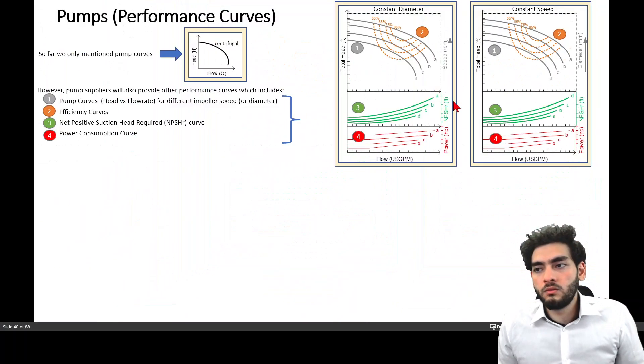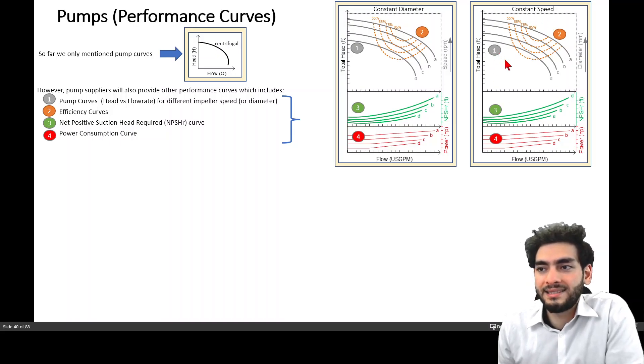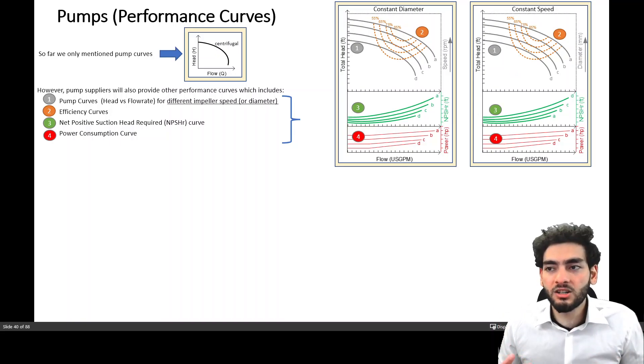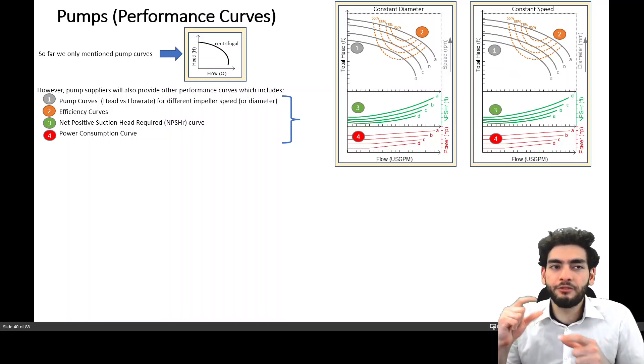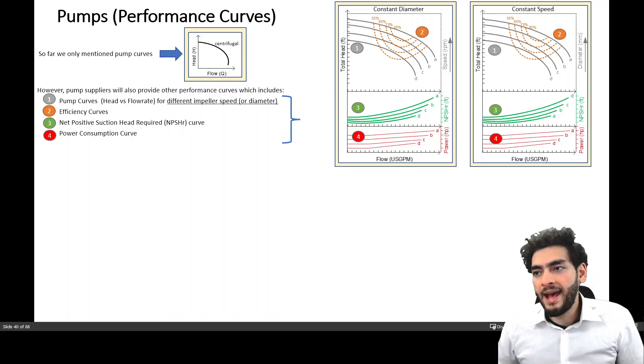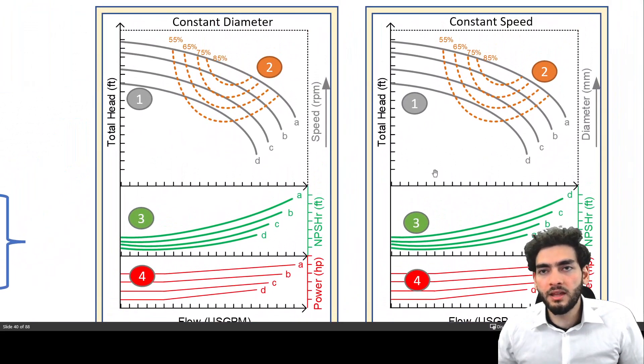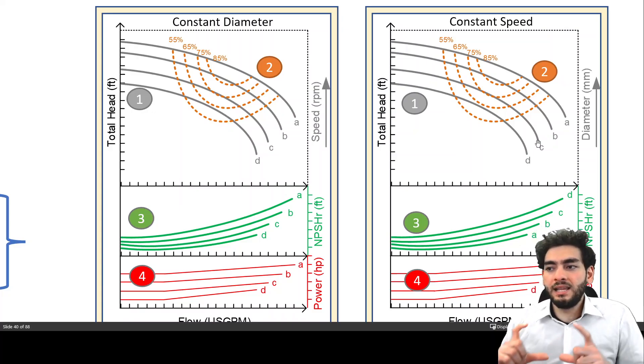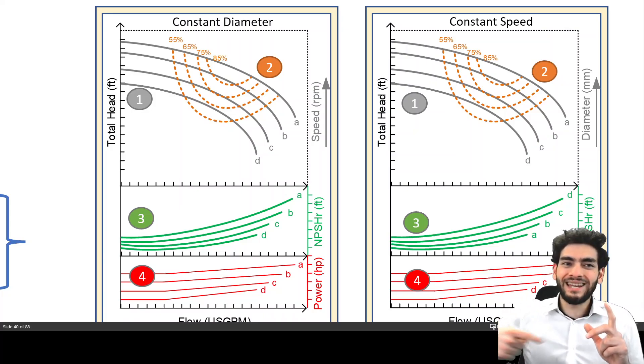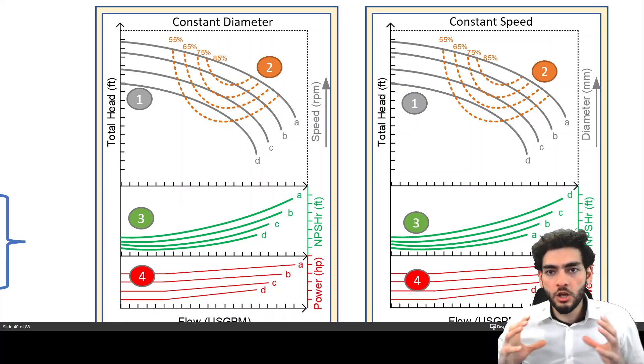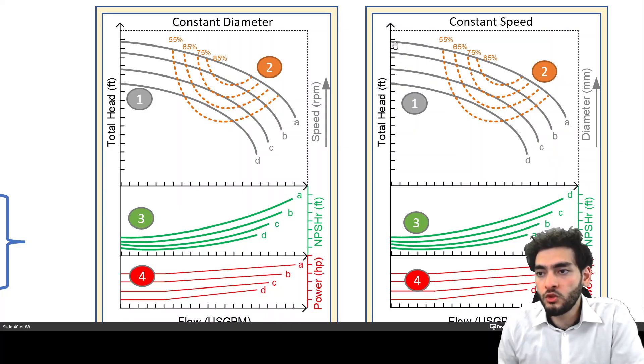Now, if we look at the graph on the right hand side, it's essentially the same performance curves, but for different impeller diameters. And let's look at them together. So if you increase the impeller diameter, what's happening is now you're providing more centrifugal force to the fluid. And so as a result of that, you will generate more head and flow rate.